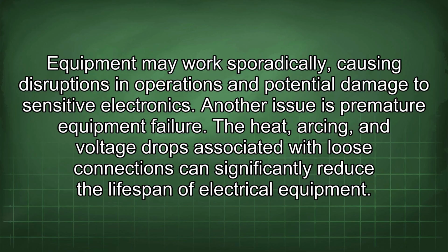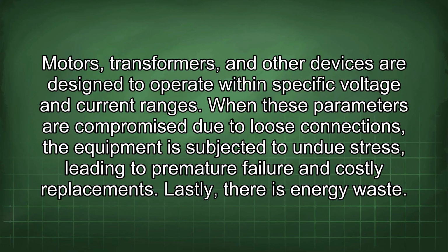Another issue is premature equipment failure. The heat, arcing, and voltage drops associated with loose connections can significantly reduce the lifespan of electrical equipment. Motors, transformers, and other devices are designed to operate within specific voltage and current ranges. When these parameters are compromised due to loose connections, the equipment is subjected to undue stress, leading to premature failure and costly replacements. Lastly, there is energy waste.